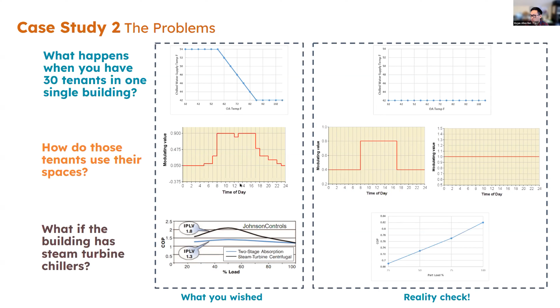And another problem is, what if you have steam turbine chillers? Those chillers have a COP of 1, if you're lucky. The reason people use those is because you can avoid the demand charge in summer, and gas is cheap, so even with a low COP, you still pay less money. But the problem is the EUI is going to be super high if you have a COP of 1. And I'm not going to talk too much about simulation. I'm going to talk about solutions here.